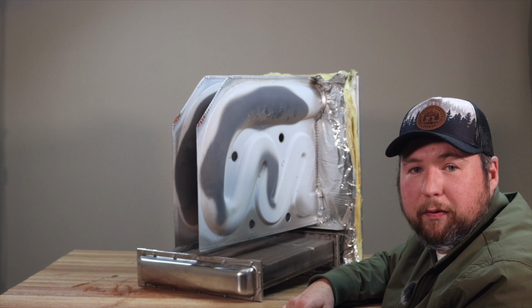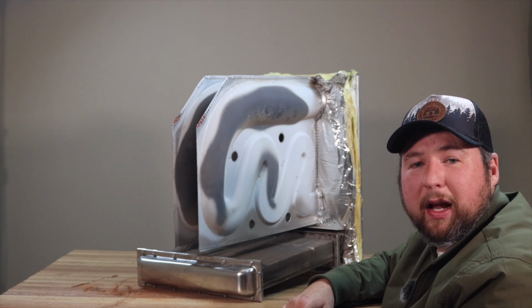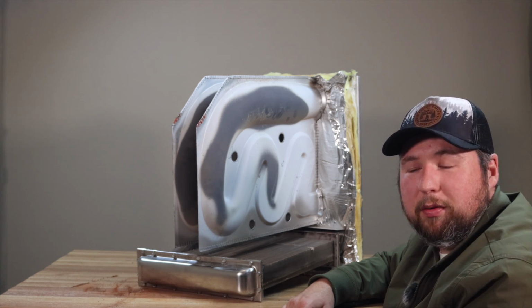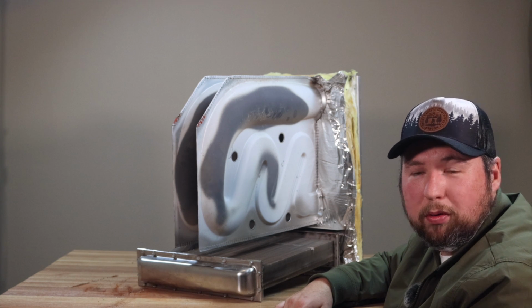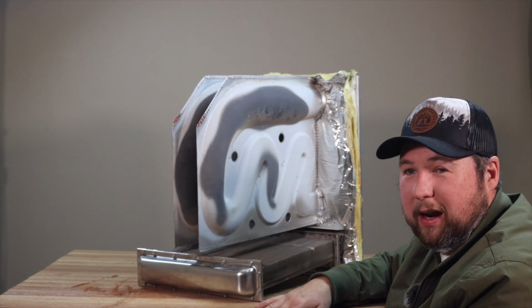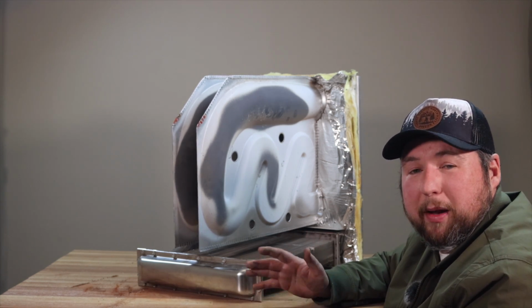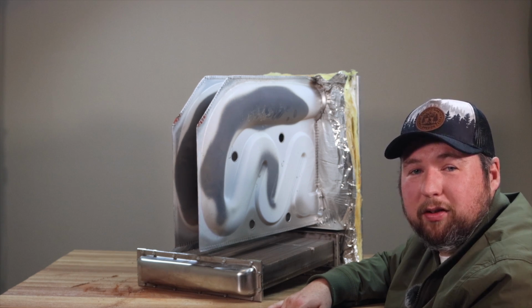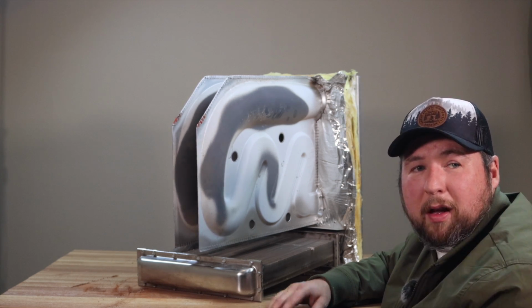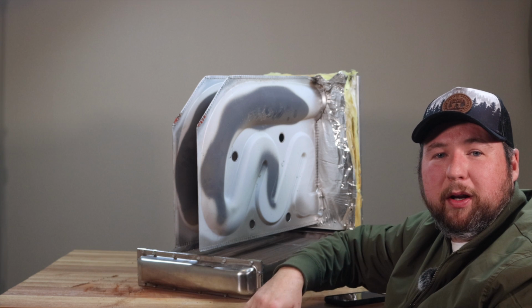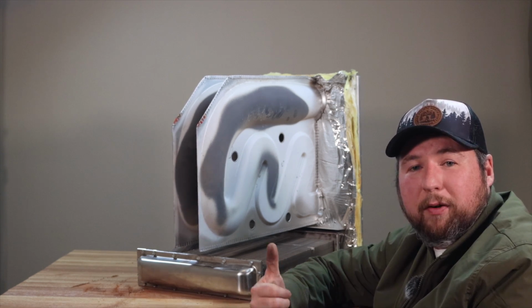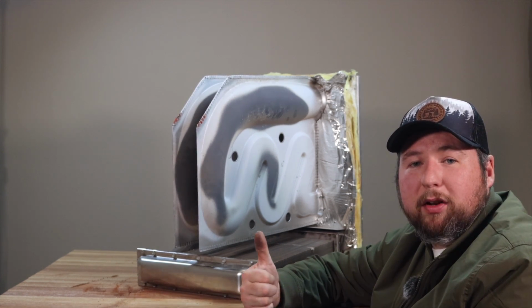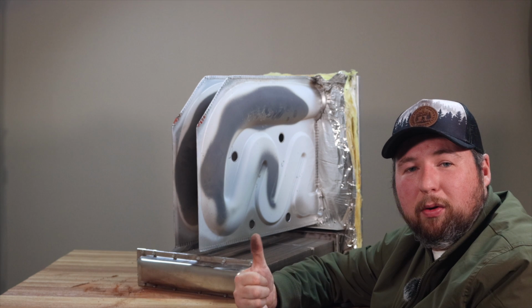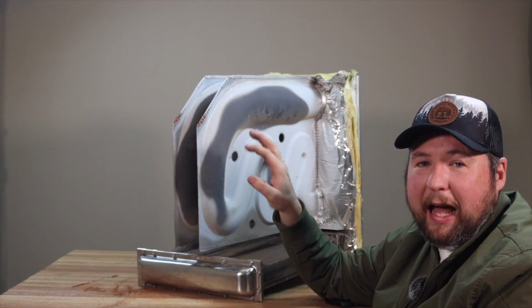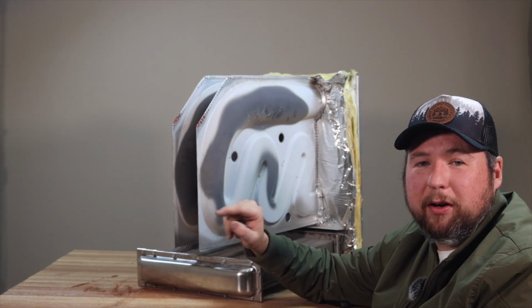And then if you do find a crack, turn it off and recommend replacing the heat exchanger. Or if the unit's old, like super old, or it's got other issues, the customer may want to consider replacing the whole furnace and just going from there. But that's pretty much what you want to be looking for when you're doing these safety inspections of your heat exchanger: you want to make sure that there are no cracks, there are no holes, because you don't want the gases in here going into your airstream.